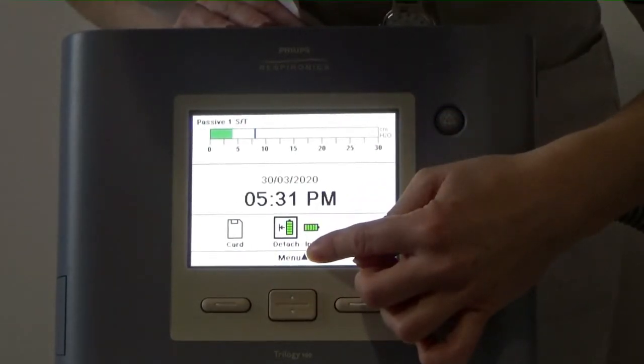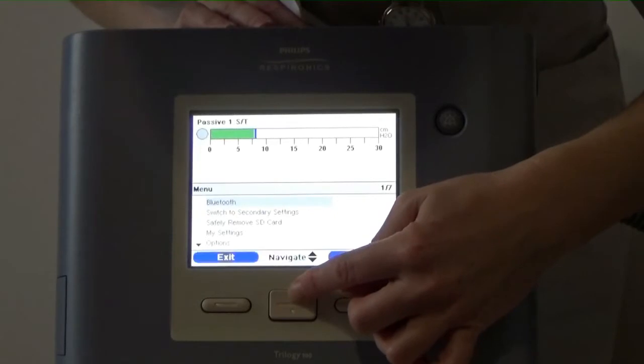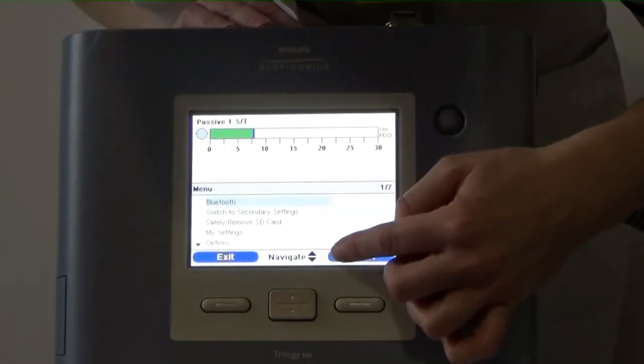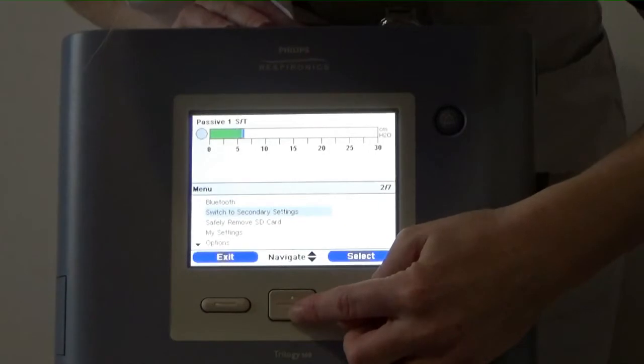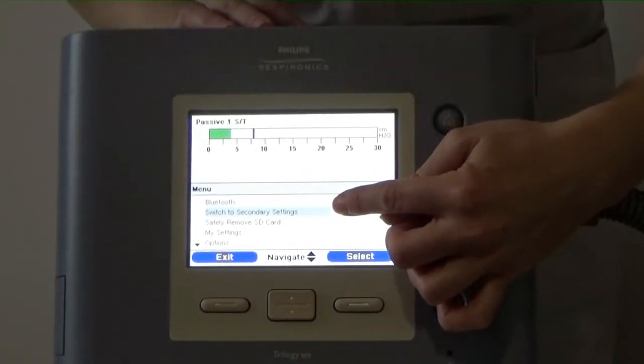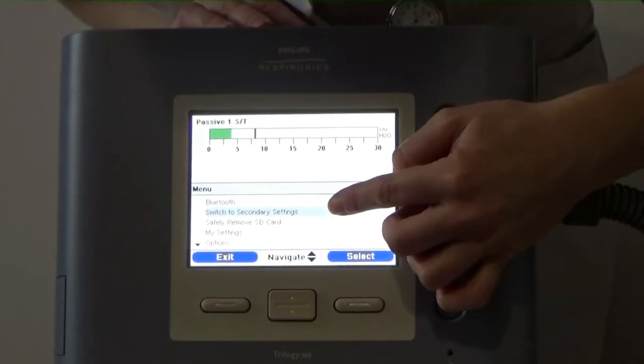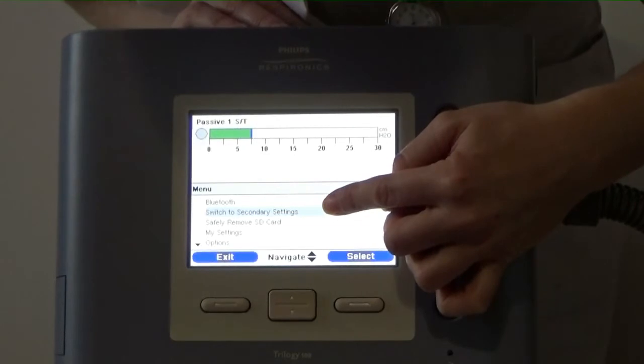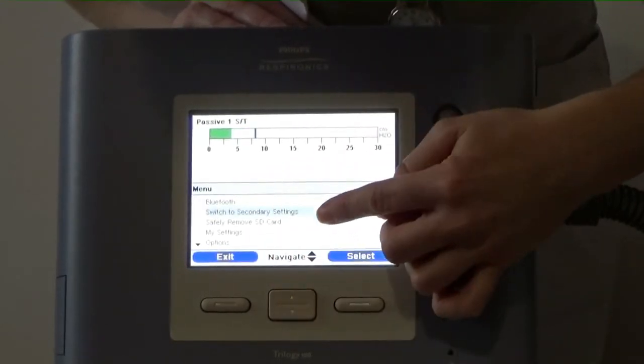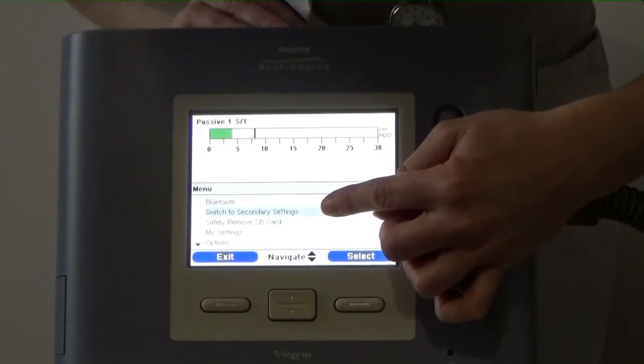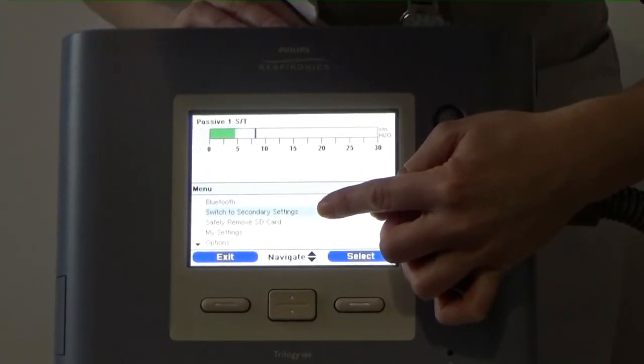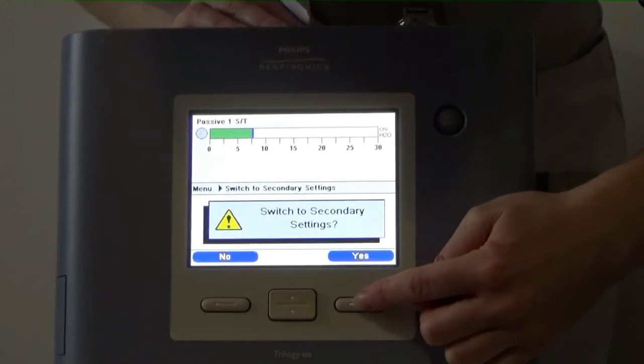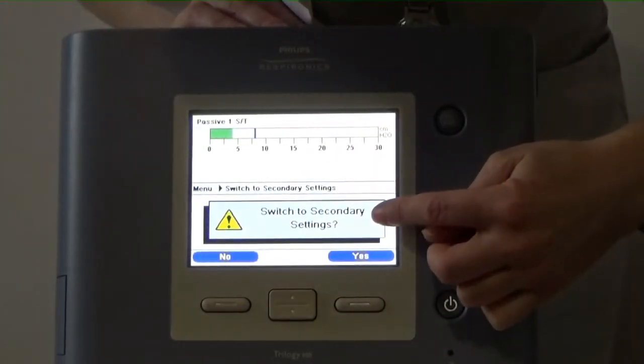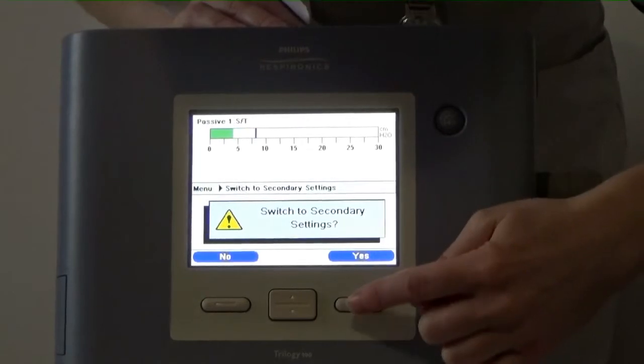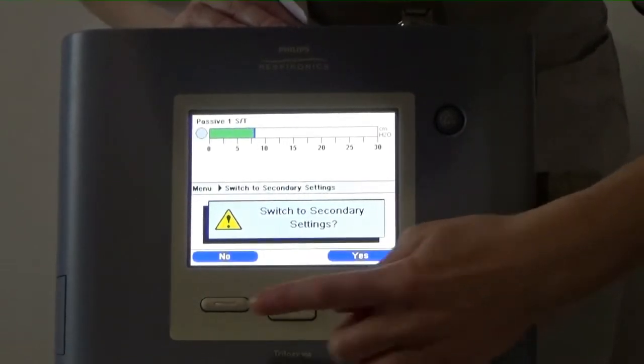Next, we can see the word menu. We can press up to access the menu. Now we can see a selection. If we press down, the first option we come to says switch to secondary settings. Some people will have a second program of ventilation set on their device, and if so, this will have been decided by a clinician. However, not everyone will have this option. If your client does have secondary settings and you need to access them, press select, and the device will ask you, do you definitely want to switch to secondary settings? In which case you would press yes. In this case, we'll press no.